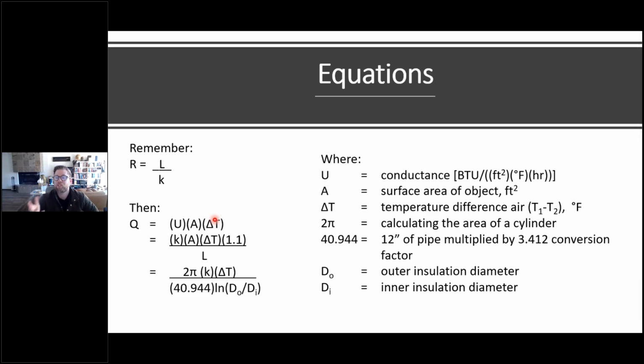fluid temperature, we make an assumption, and we have to make assumptions to kind of simplify this process a bit. There's going to be a delta T there. So assuming, let's say, our fluid temperature is 140 degrees, let's make the assumption that 140 degrees is what's on the inside of the insulation, that the copper wall is basically 140 degrees Fahrenheit. And so the inside wall of the insulation is 140 degrees. And then we're going to make the assumption that the outside wall is, let's say, 65 degrees Fahrenheit. Let's say it's a cold plenum space that the pipe is sitting in. So you have 65 degrees Fahrenheit as the second temperature. And that's going to calculate out what your heat transfer is.